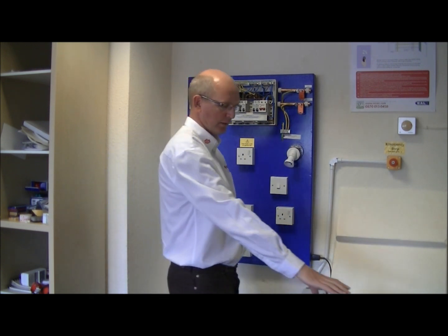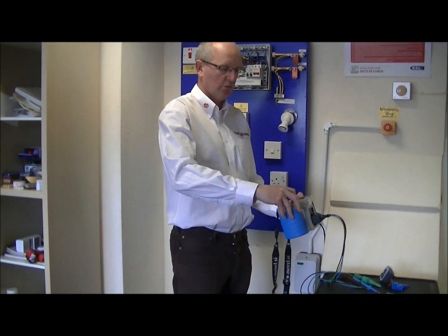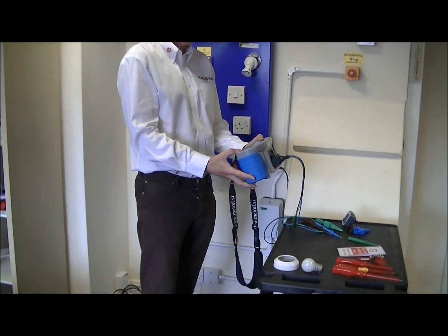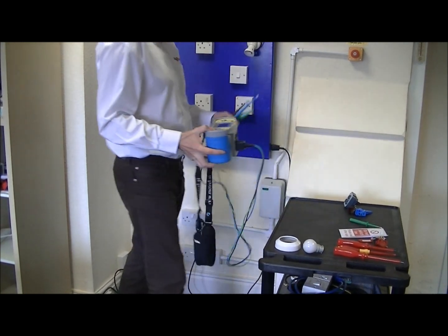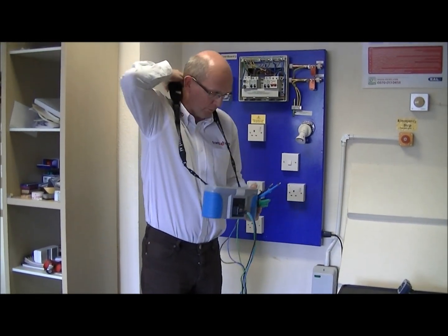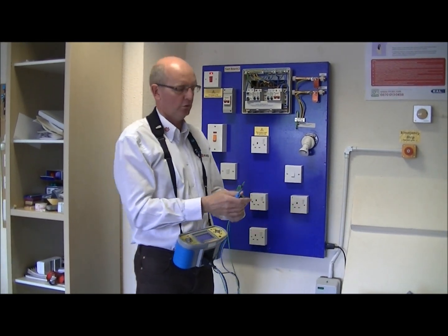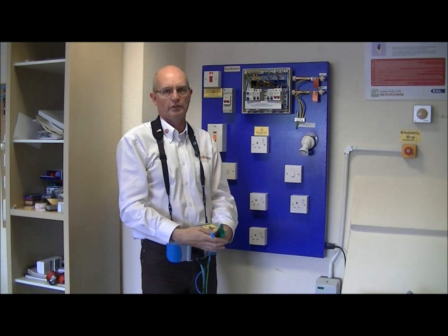In this video I'm going to demonstrate how we carry out an earth loop impedance test on a final circuit, otherwise known as ZS. So we have our multifunction tester here, which we select to perform the earth loop impedance test, and we need to measure at the furthest point on the circuit. So this is a live test, and we carry out this test to ensure that we meet the maximum disconnection times for our protective devices.